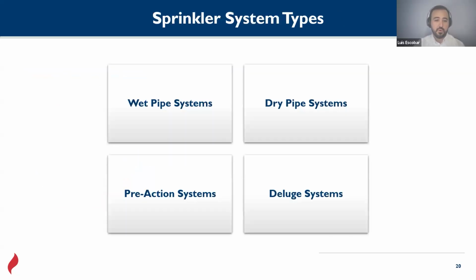We have 4 types of sprinkler systems: wet, dry, pre-action, and deluge. This type of system is going to be probably 90% of the systems that we design in the fire industry. Well, probably not 90, 80, let's say 80. But it's a large amount of projects because it's indoor, right? We're going to go over those very quickly.